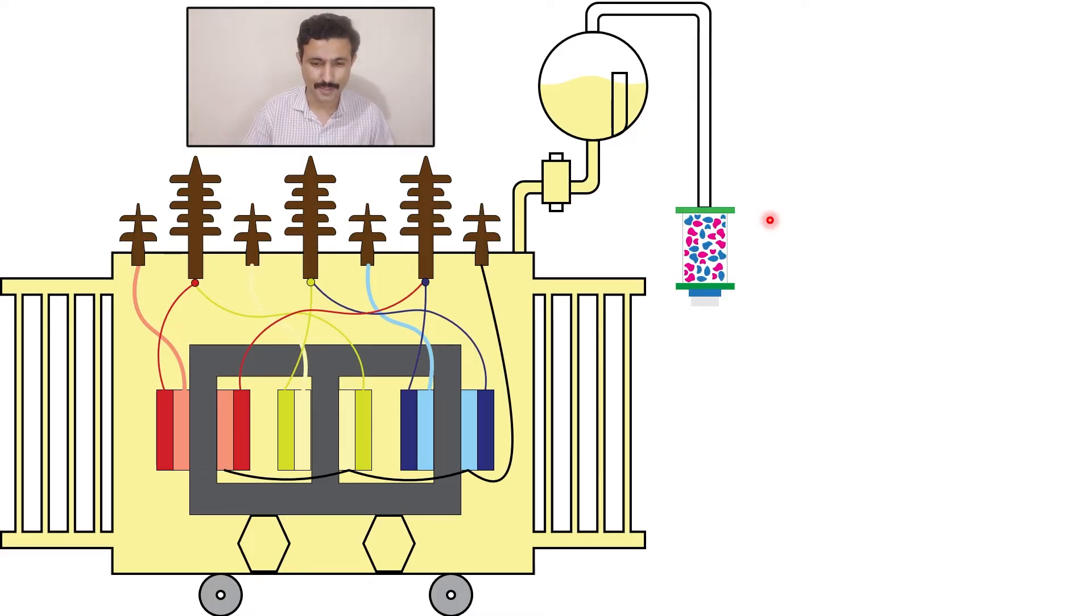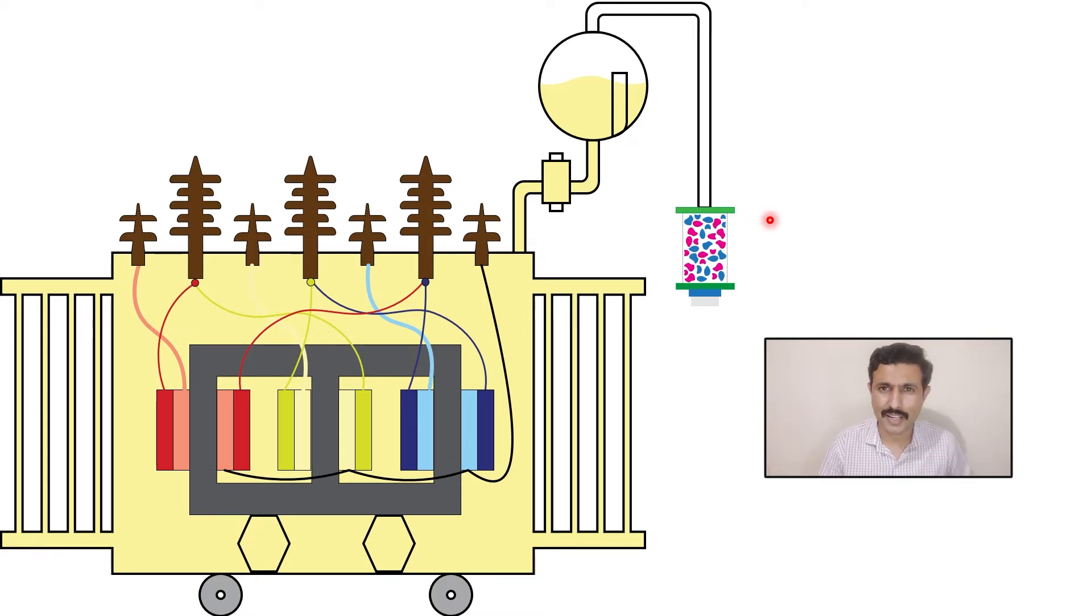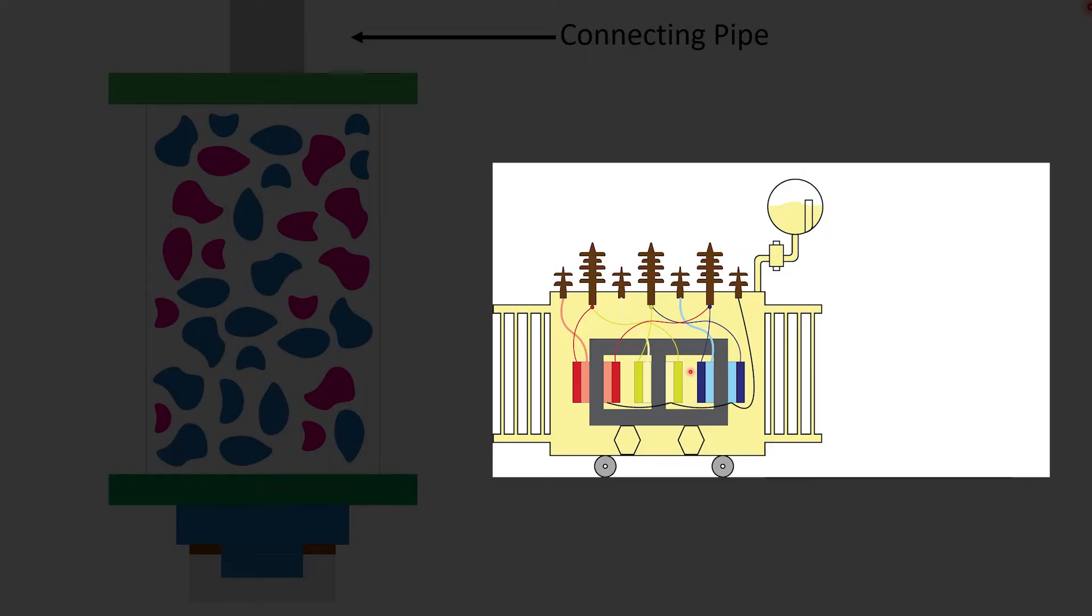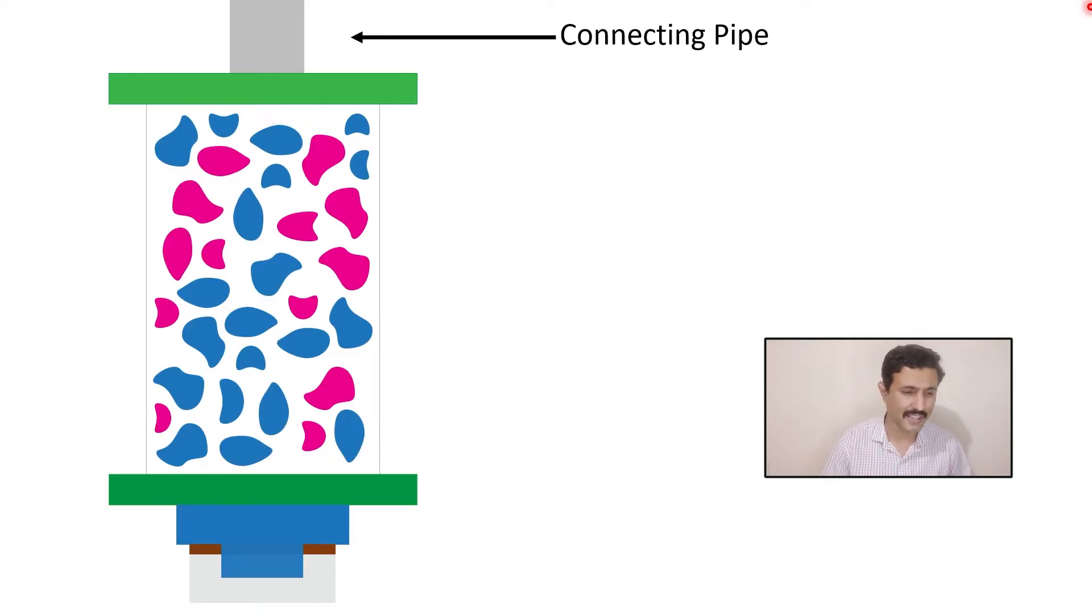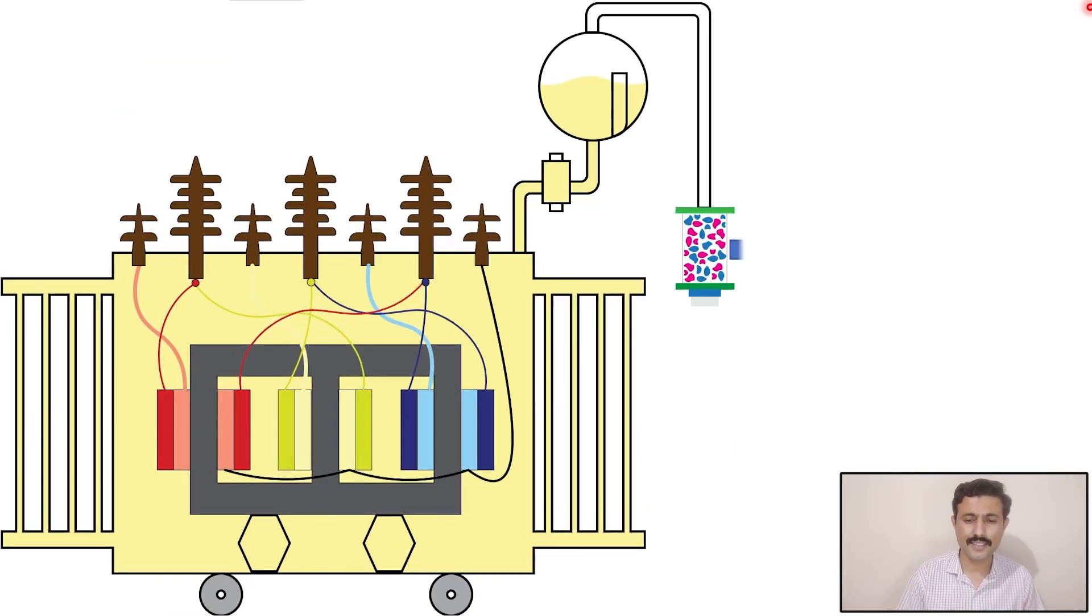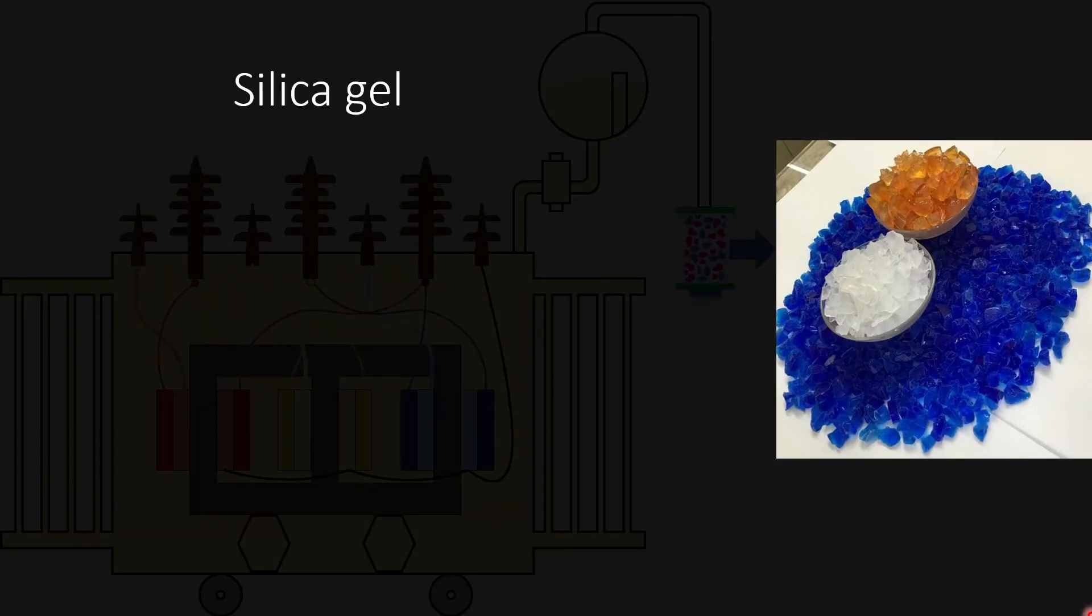This breather plays the role of hero when we are tackling the moisture. Now let's deep dive into the breather. This is the breather. This is the connecting pipe through which the breather is connected with the conservator tank. There are top lid and bottom lid, and in between these two there is a transparent cylinder. In this transparent cylinder, silica gel is filled. This is the real image of silica gel.